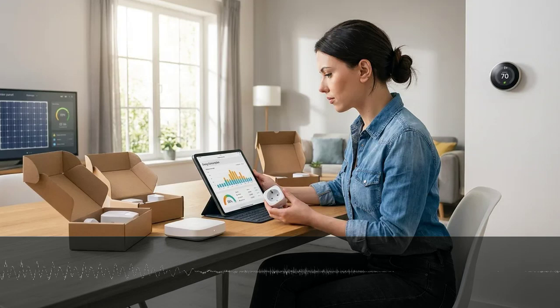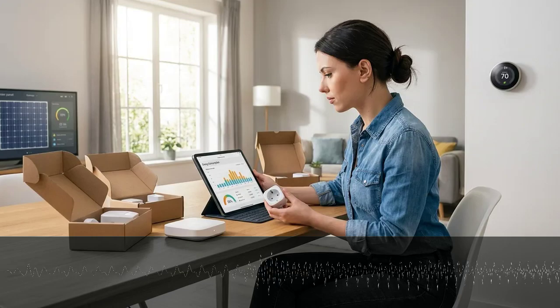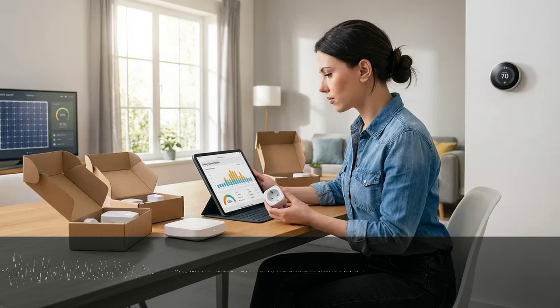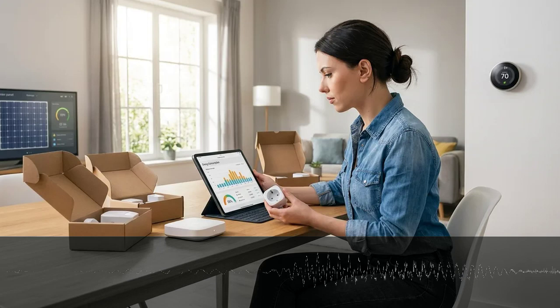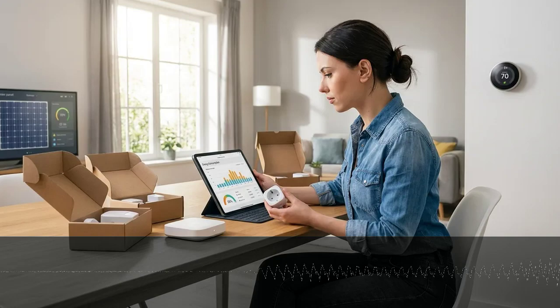Some utilities charge based on peak demand, which is the highest 15-minute average draw per billing cycle, in addition to energy consumption. Load balancing automation looks like this. If current demand is greater than 8,000 watts, which is a threshold below the utility penalty tier, and EV charging equals true, then pause EV charging for 15 minutes, wait until current demand is less than 6,000 watts, then resume EV charging. This prevents expensive demand charge tiers. My utility charges $12 per kilowatt for demand above 10 kilowatts. Avoiding one 12-kilowatt spike saves $24 per month.